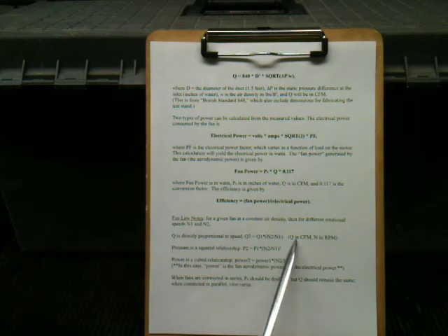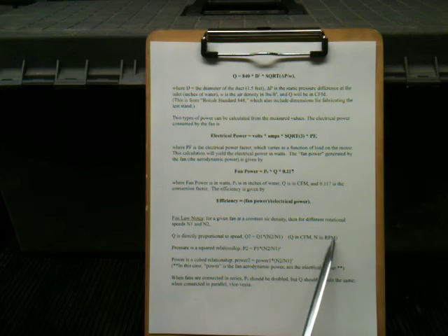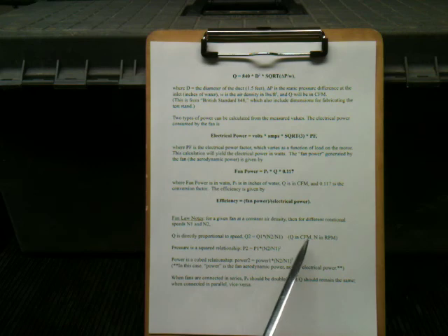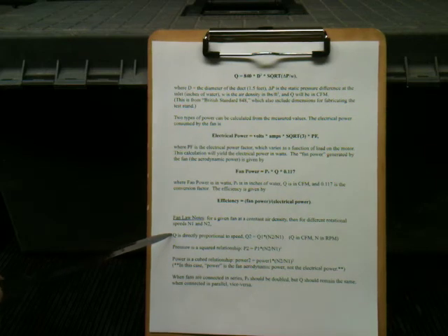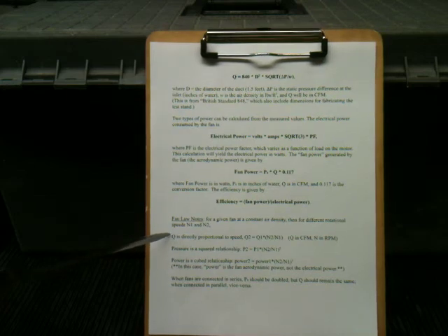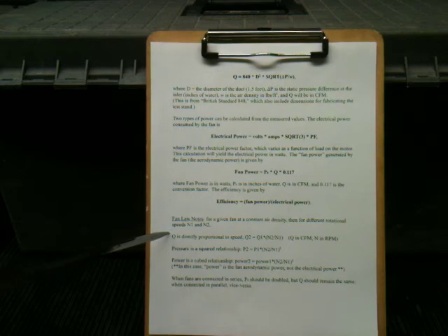And again, Q is in CFM and N is in RPM. So Q you're going to calculate from this equation. RPM is measured. So you want to look at this relationship from the two cases of single fans, so look at the two cases of the 10 horsepower fan, see if this holds true, and the two cases for the single 5 horsepower fan, again, low speed and higher speed.